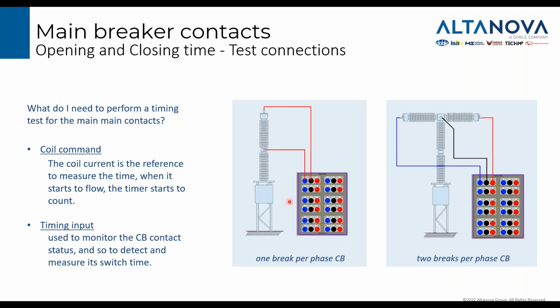What do I need if I want to perform this test? For example, I can connect the main contact to a timing input of any standard circuit breaker analyzer, and as well I have to connect the coil command, because I need to control the moment where the command is issued, because in that moment I have to start the timer. So I give the command, I start the timer, and I check when this resistance changes status through this dedicated input.